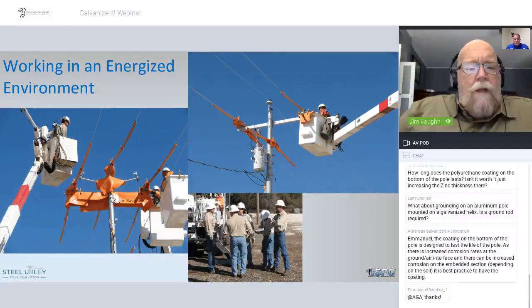One of the things that we teach is I&I, insulation and isolation, and that's what's going on here in this picture on the left-hand side. You'll see all the cover that's there. So I want to talk to some of the linemen that might be out there looking at this, and you say, man, that's an awful lot of cover. Well, this is actually exactly what OSHA intends when it comes to cover up on a pole when we're moving these conductors. See, if they're going to untie these conductors and move them around, losing control of this conductor will put it against the arm or against the pole. And that's the purpose of using this cover.